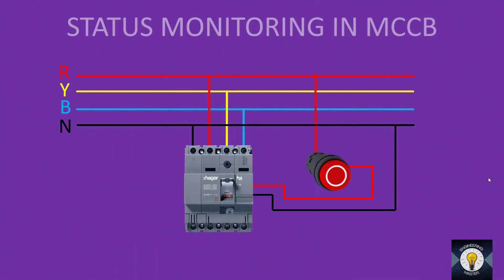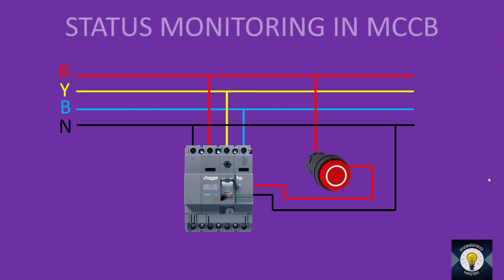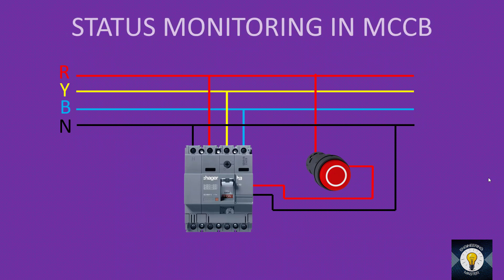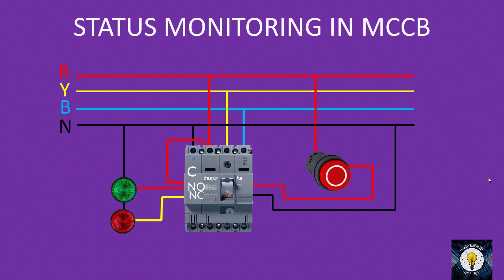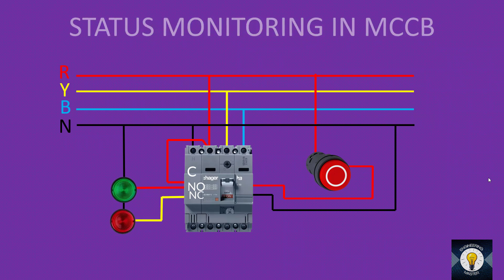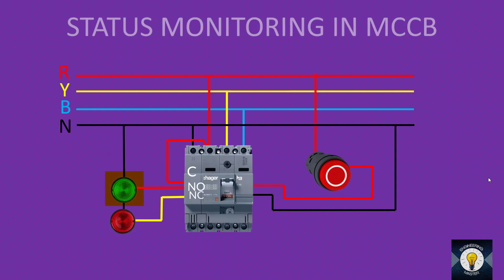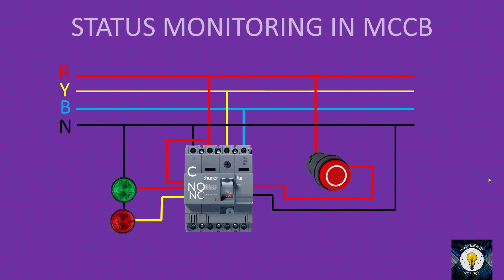To monitor the status of MCCB when the panel is at a remote location, auxiliary contact blocks are used. Some MCCBs come with them inbuilt; others require inserting an auxiliary contact block. Connect two lamps — green and red — with neutral looped to both lamps and a single phase to the common terminal of the auxiliary contact block. The NO (normally open) terminal connects to the green light and the NC (normally closed) connects to the red light. In normal ON condition, the green light is lit. When the emergency push button trips the breaker, the contact switches to NC and the red light is lit.